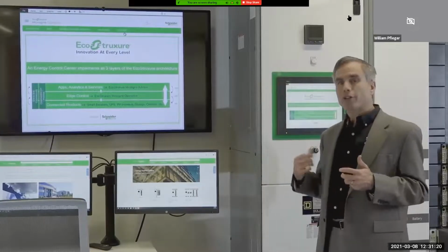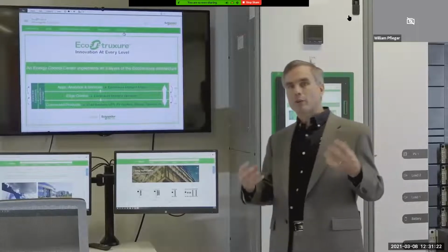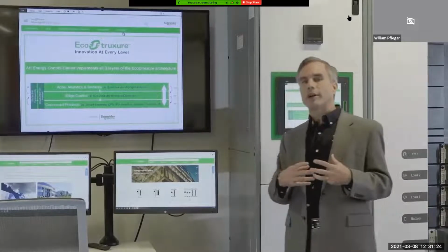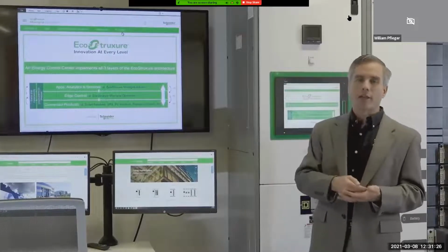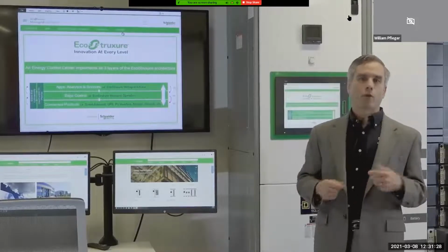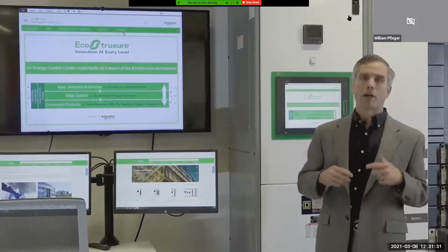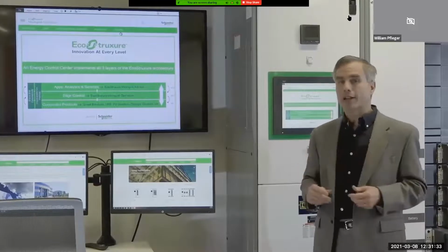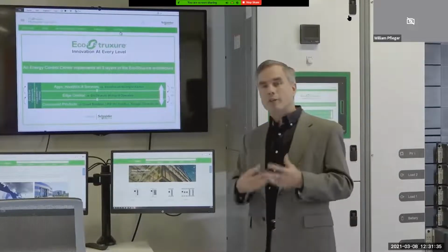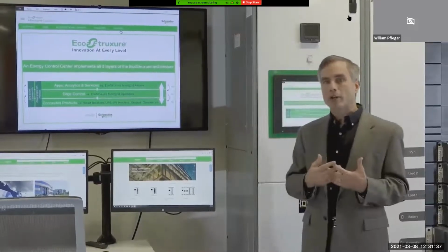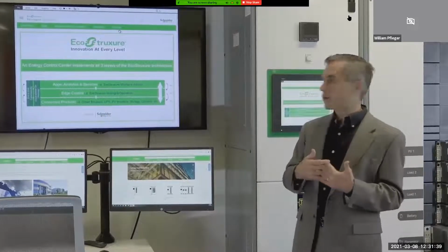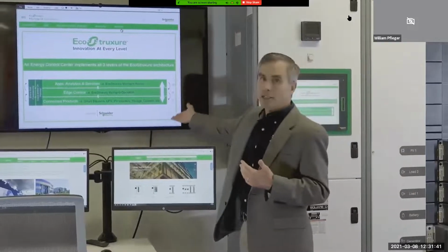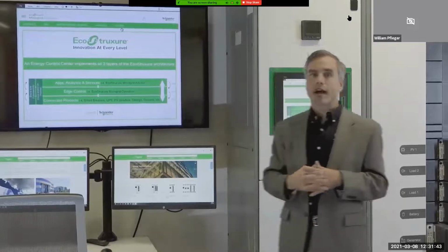But it turns out these smart breakers have little embedded power meters built into them. So they know not only the current, but the voltage, and therefore the power, the reactive power, the frequency, the power factor—you name it. All the great information you could pull from a power meter, we can pull from these smart breakers and have that information flow up to other layers of the stack.